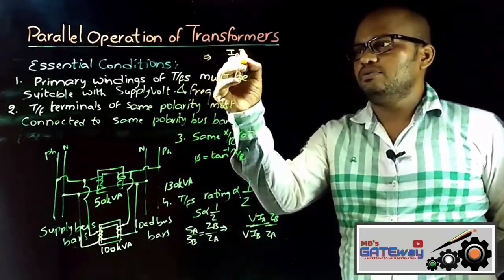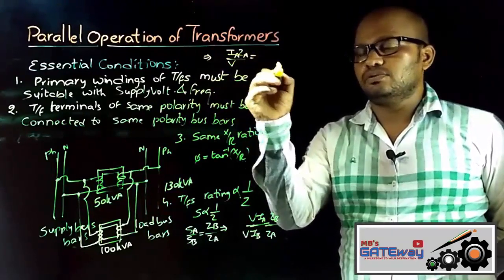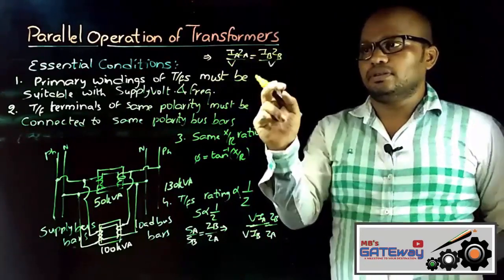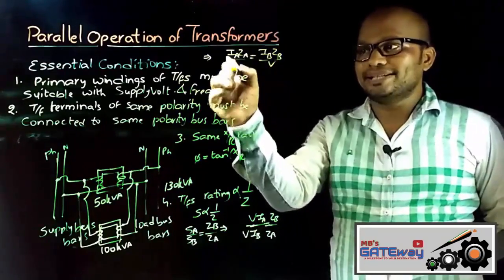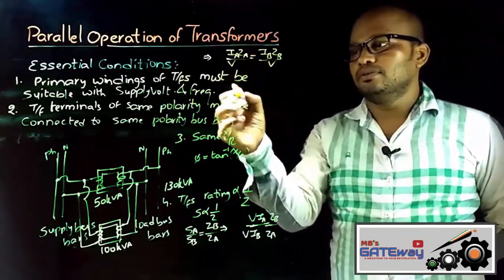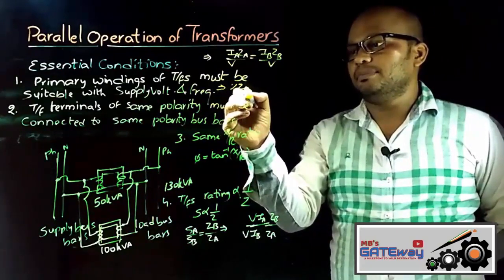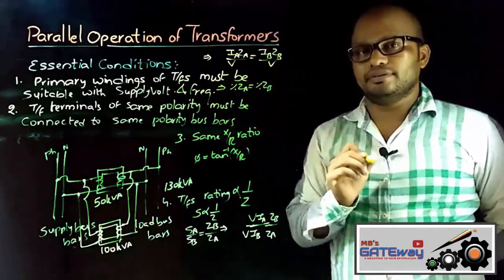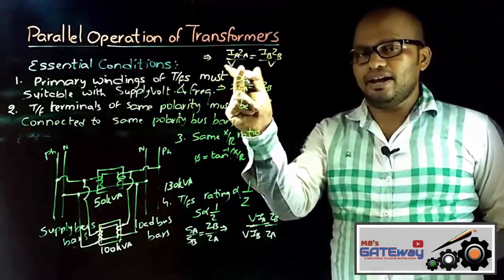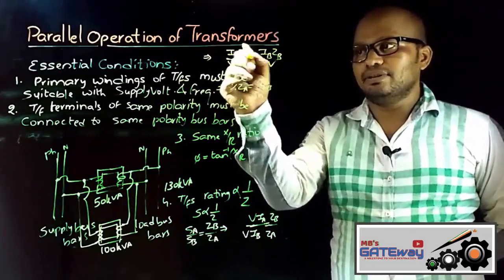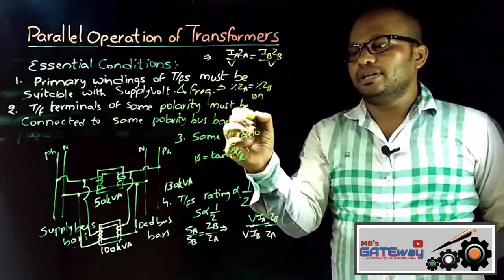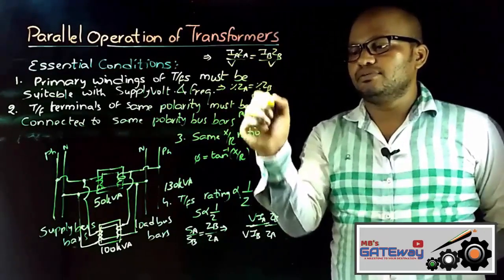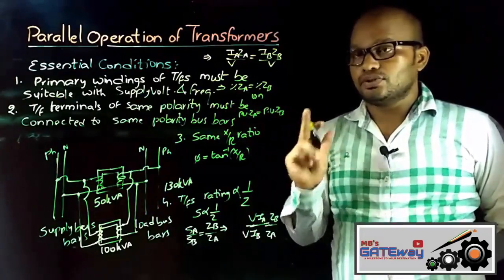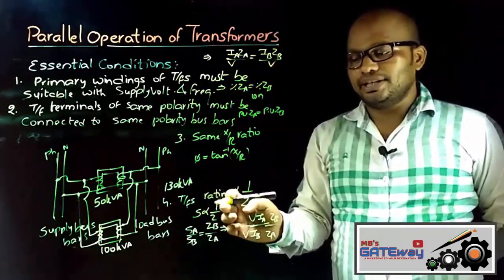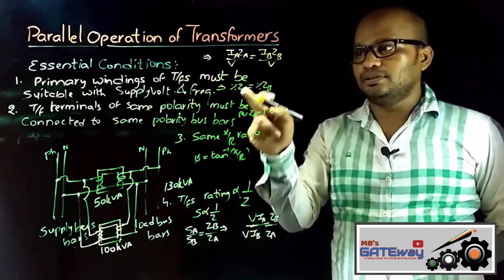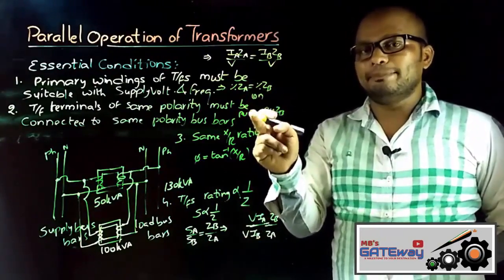Which implies IA into ZA by V is equal to IB into ZB by V, and if you multiply by 100 on both sides, that will give you the percentage impedance drop, which can simply be termed as percentage impedance. So percentage impedance of A is equal to percentage impedance of B, or you can represent it as ZA by V by IA. So V by IA is the base impedance, and this will represent the per unit impedance. So you can write the per unit impedance of transformer A is equal to the per unit impedance of transformer B. So the fourth condition can be termed as either the transformer ratings must be inversely proportional to their impedances, or their percentage impedances must be equal, or their per unit impedances must be equal.